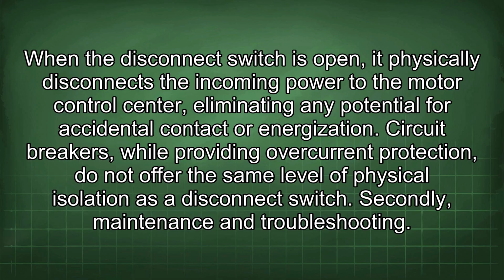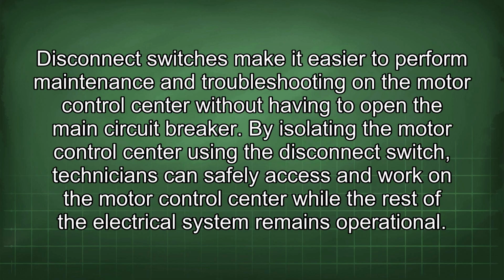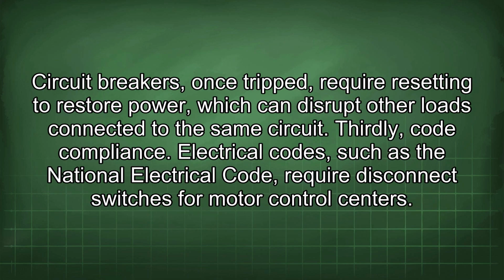Secondly, maintenance and troubleshooting. Disconnect switches make it easier to perform maintenance and troubleshooting on the motor control center without having to open the main circuit breaker. By isolating the motor control center using the disconnect switch, technicians can safely access and work on the motor control center while the rest of the electrical system remains operational. Circuit breakers, once tripped, require resetting to restore power, which can disrupt other loads connected to the same circuit.